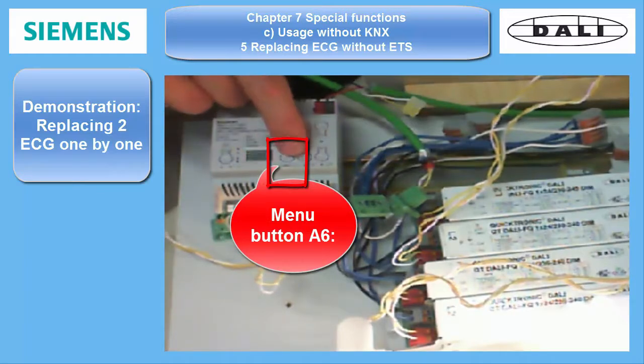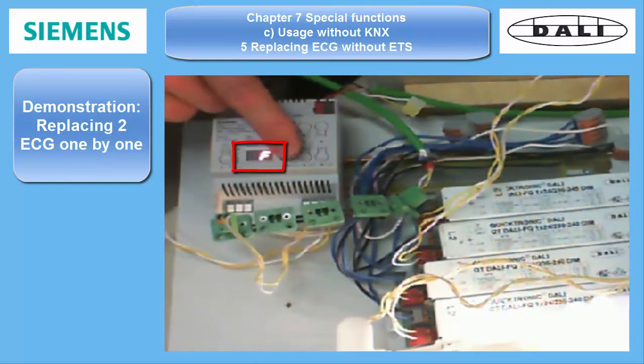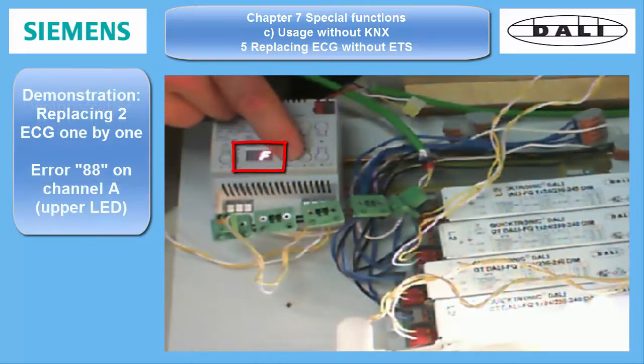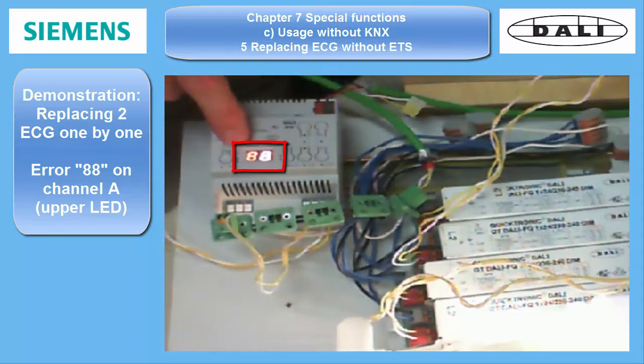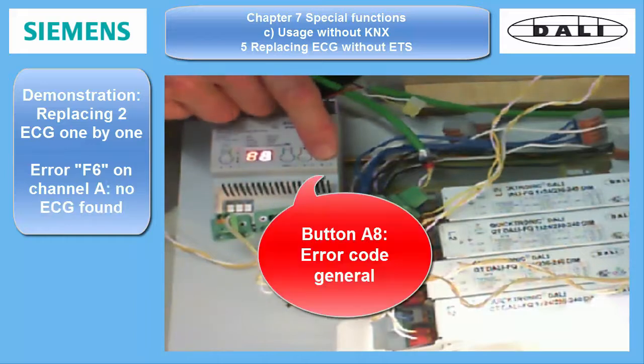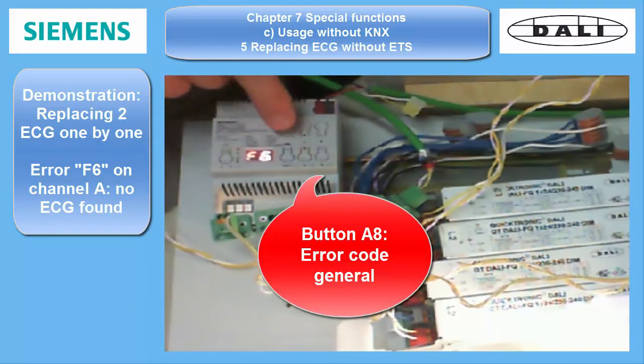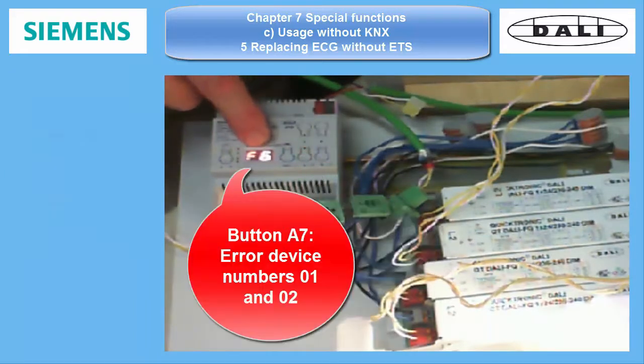The F remains. Press A6 again. The channel LEDs turn on according to the found errors, and 88 appears on the display, meaning the first error can be shown now. To see what error code it is, press one of the A8 buttons on the right. Here we find F6. It means no ECG found.